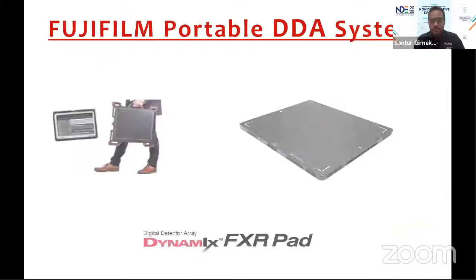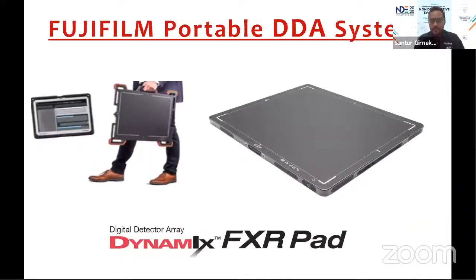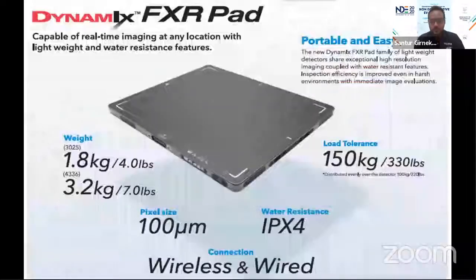The second one is the portable DDA system. It's a very handy digital flat panel detector. It weighs around 1.8 kg and up to 3.2 kg depending upon the model, and it can tolerate a load up to 150 kg. The pixel size is 100 micron and IPX4 grade. You can connect this detector in both wireless and wired mode. Basically, we can use it in applications at off-site locations.